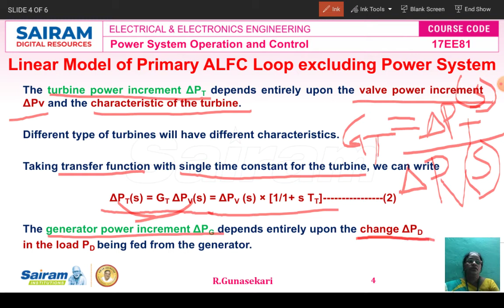Now, continuing the linear model of the primary ALFC loop, the generator always adjusts its output to meet our load changes ΔPD. The adjustments are essentially instantaneous, that means the generator output ΔPG changes instantly in comparison with the slow changes in the turbine power PT, because the turbine and the generator are both mechanically coupled on the same shaft. So if we can control the turbine, automatically we can control the generator. In this view, ΔPG equals ΔPD.